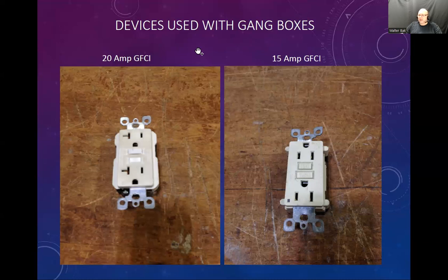It is not enough, because you need to make sure that the gauge of the wires between the circuit breaker and the receptacle is also capable. It also has the ampacity, which means the capability of handling a certain amount of current.